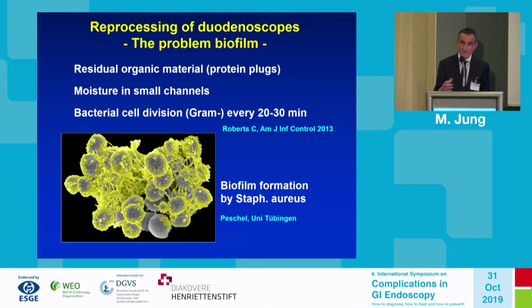Biofilm means that bacterial plaques can be surrounded by organic material and by mucopolysaccharides. The mucopolysaccharides form a fixed covering around the bacteria, and they may be resistant to every part of reprocessing, in particular to brushes. So the problem of biofilm, which can only exist in the presence of liquid, is one of the main problems in reprocessing. The endoscope has to be completely dry at the end, and all the small protein plaques, bacterial and blood formations after the endoscopy have to be removed by extensive cleaning.